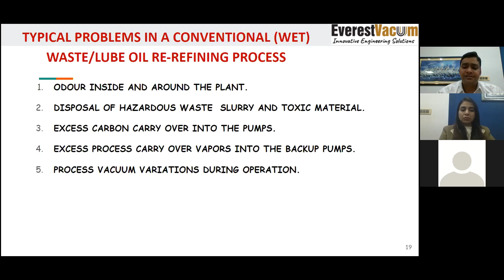Process vacuum variation during operations. All these steam ejectors and water jet ejectors are entirely dependent on some fluid, which is majorly steam in ejectors, and in water jet it's water. These have properties to fluctuate based on the backup being provided. Sometimes we have seen that steam is required in some other section of the plant, so we have shifted the steam to some other location, which results in lower pressure and quantity, resulting in fluctuations in the vacuum and displacement. These can be maintained well in the plant, but the persons operating them have no control on the figures floating in the ejectors. So this is one of the obsolete processes which everyone is now moving out of, seeing the steam cost and the PCB norms.